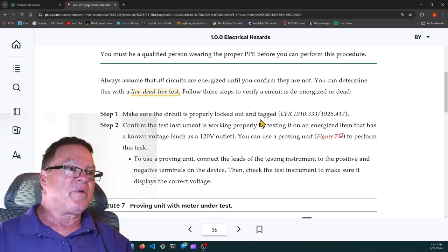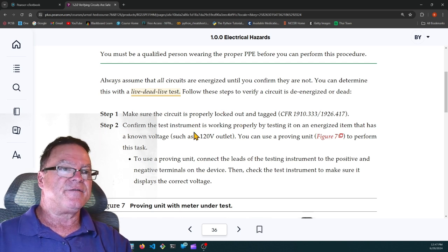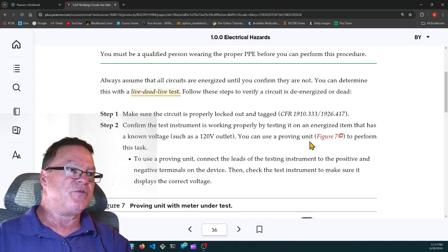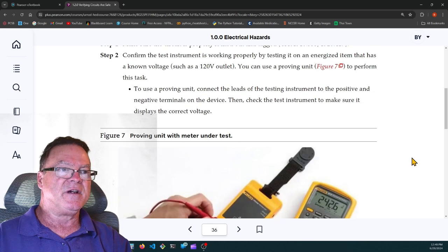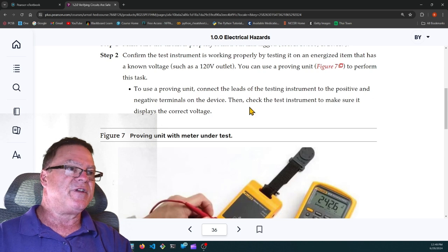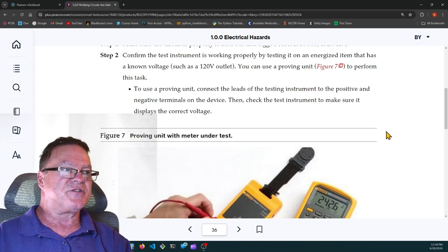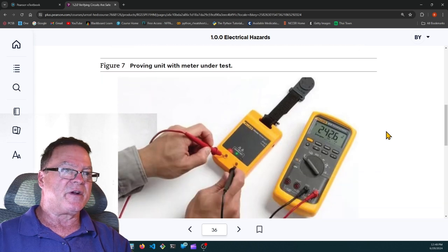Make sure the circuit's properly locked out and tagged. Confirm the test instrument is working properly by testing it on an energized item that has a known voltage. You can use a proving unit to perform this task. To use a proving unit, connect the leads to the testing instrument to the positive and negative terminals of the device, then check the test instrument to make sure it's displaying the correct voltage.